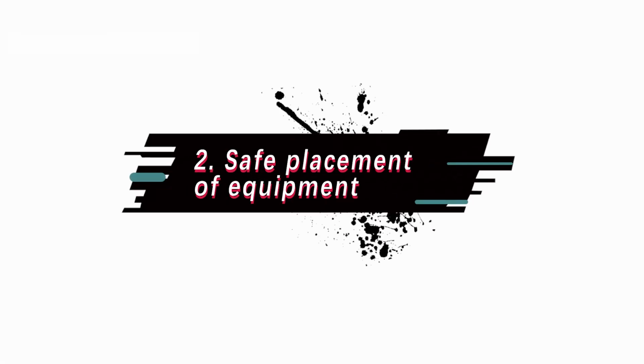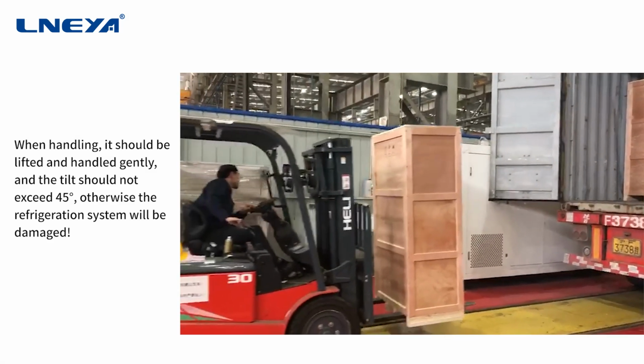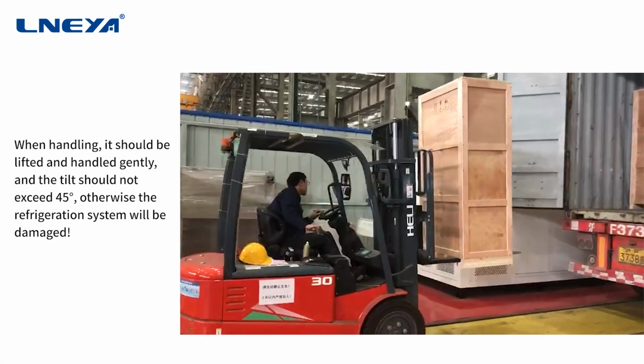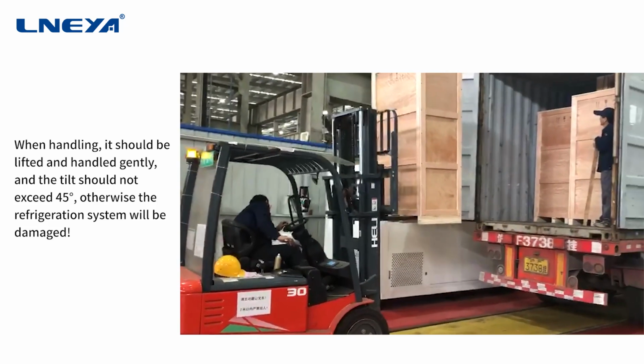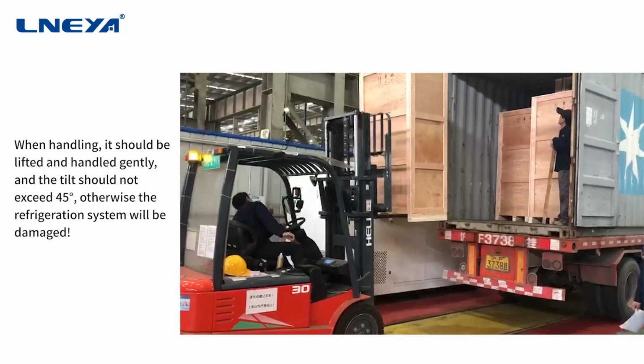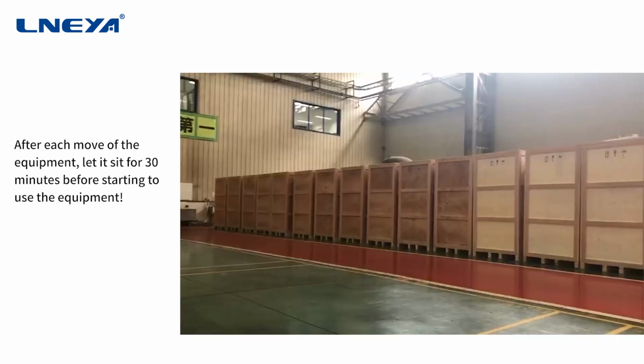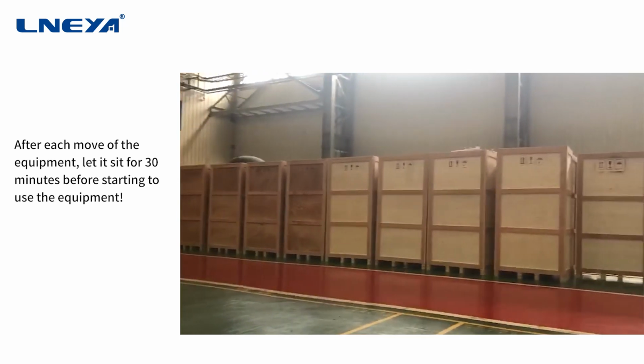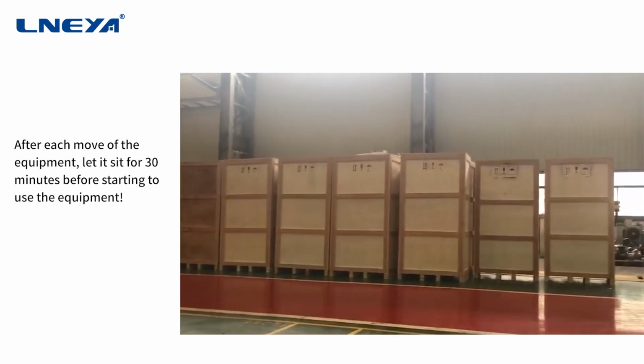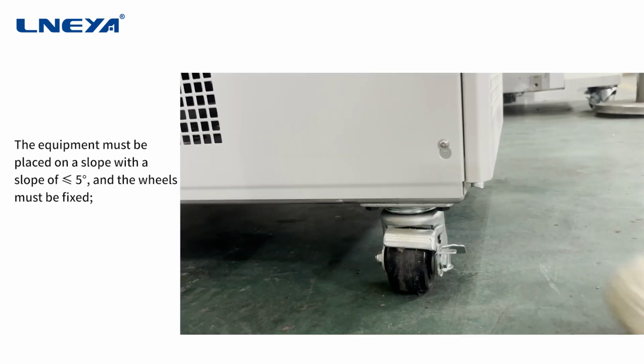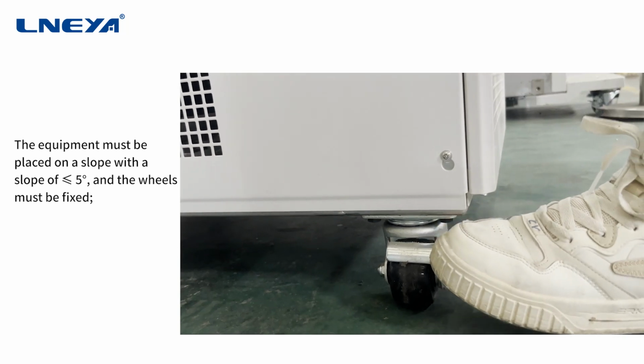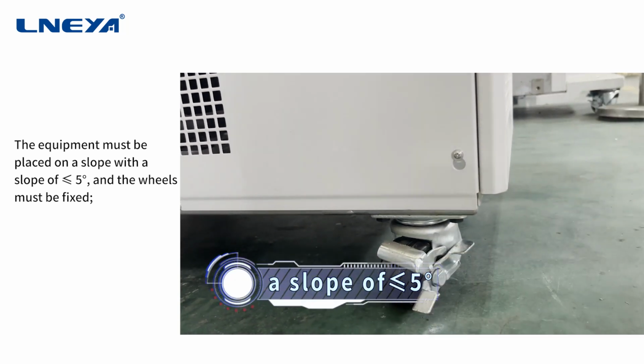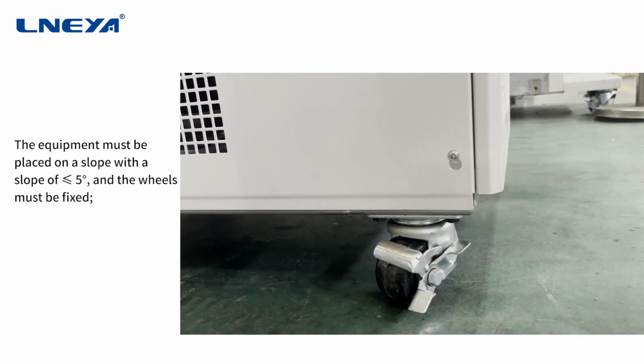2. Safe placement of equipment. When handling, it should be lifted and handled gently, and the tilt should not exceed 45 degrees, otherwise the refrigeration system will be damaged. After each move of the equipment, let it sit for 30 minutes before starting to use the equipment. The equipment must be placed on a slope with a slope of less than or equal to 5 degrees, and the wheels must be fixed.